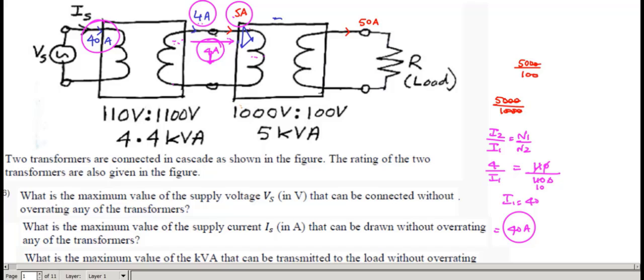Now look here again. The primary of the second transformer has a supply voltage of 1000 volts, while the secondary of the first transformer has a voltage of 1100 volts. Since there is no resistance between them, whatever voltage is generated here applies directly to the primary. So you have 1100 volts on one side and 1000 volts on the other.